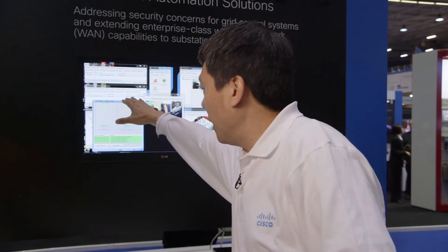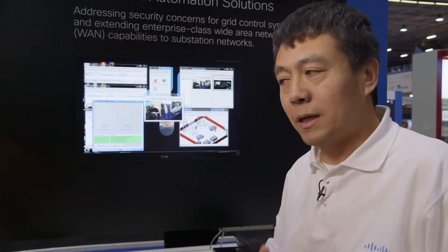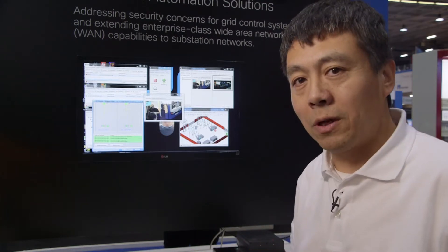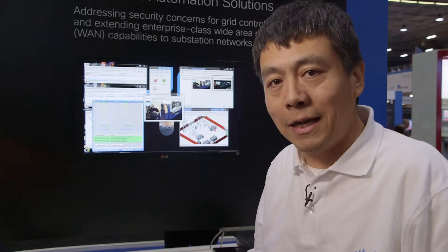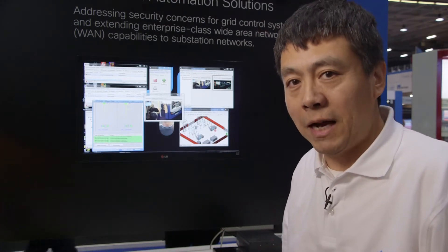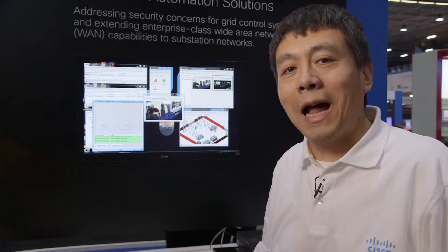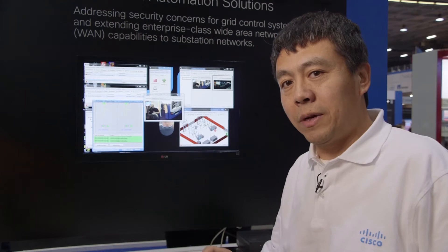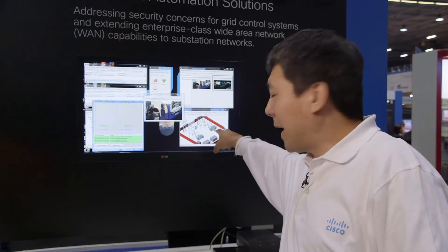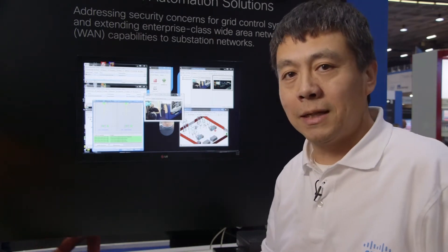As we also noticed, the event has been received from the central location where we have all the detailed information about the IED, location, and the timestamp. At the same time, a live video stream is popped up, which tells us the exact situation reflected in this alarm inside the substation.